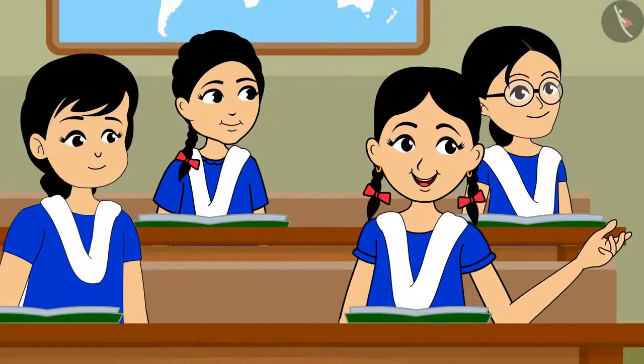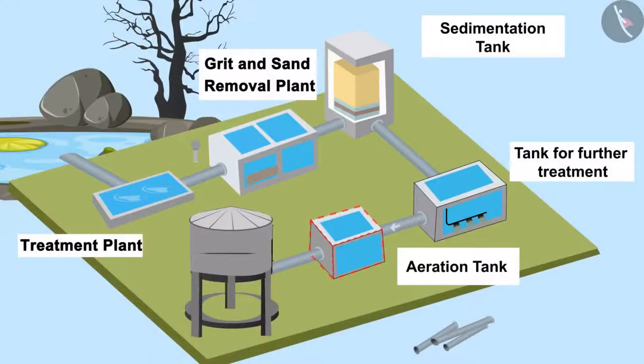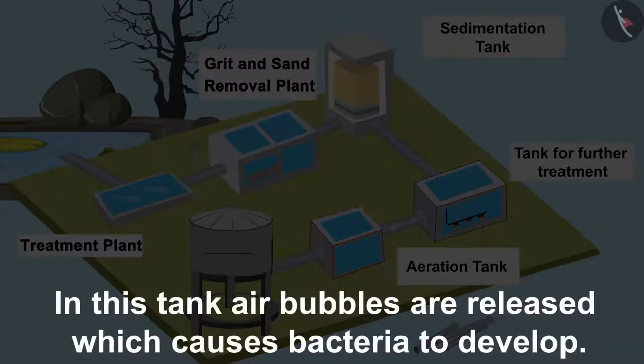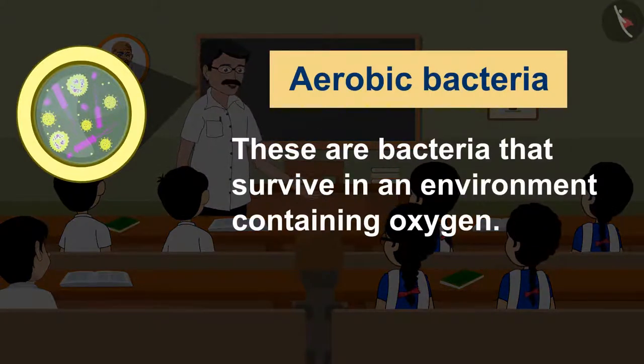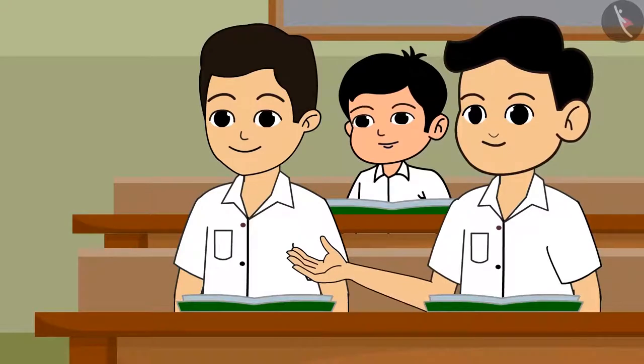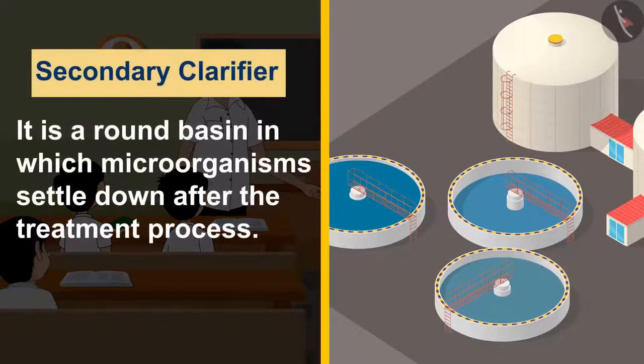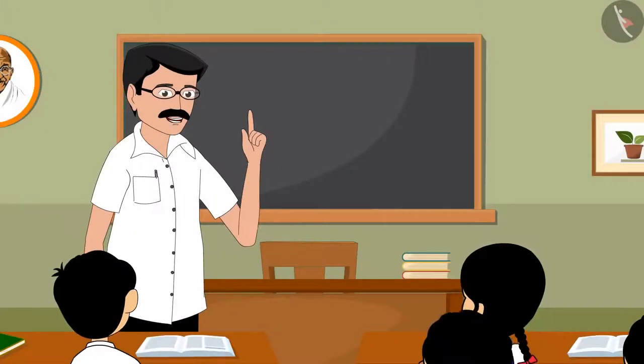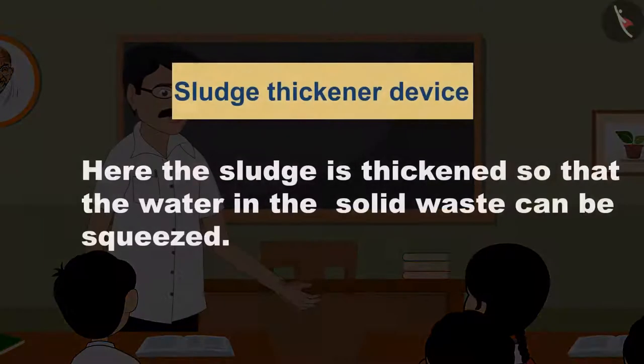The water is mostly clean with this step. After this, the water goes into an aeration tank for the second stage of treatment. In this process, aerobic bacteria are used for treatment. Organic materials are decomposed by aerobic bacteria. Bacteria eliminates the degraded substance by consuming it as food. It means bacteria are useful for us. This process clears water to a great extent. From here, water goes to the secondary clarifier. Here, the biological waste is separated. Water is treated with chlorine and is used for irrigation, flushing, etc. The remaining water is sent to rivers and seas.